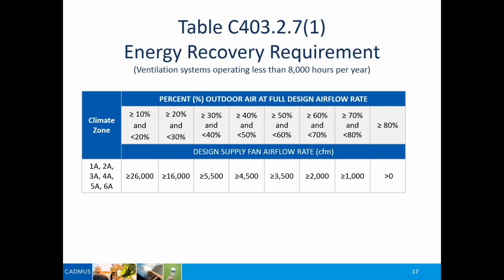That used to be in the earlier codes: you had a threshold for CFM of fan system and outside air, and if you exceeded both of those, then you had to put an energy recovery ventilation system on. The new code requirement is based on the number of hours per year a ventilation system is operating. From a code enforcement standpoint, this might be a little bit tricky, because you're going to have to ask the designer how often the space is going to be occupied, what's the intent behind the space, and do a sanity check to see if the answer matches the building. Obviously, if you have a church, you can assume the space is occupied at least one day a week, maybe more.